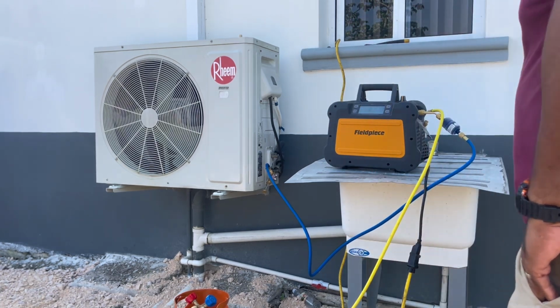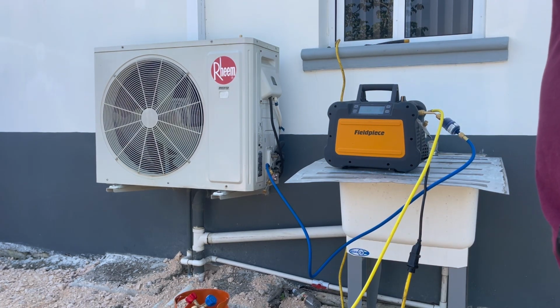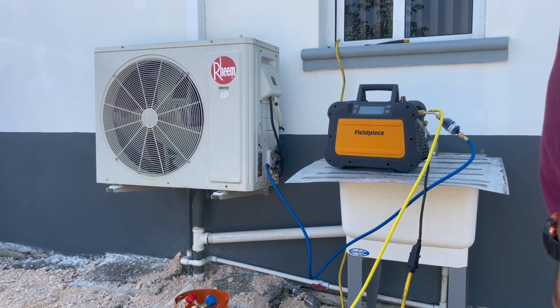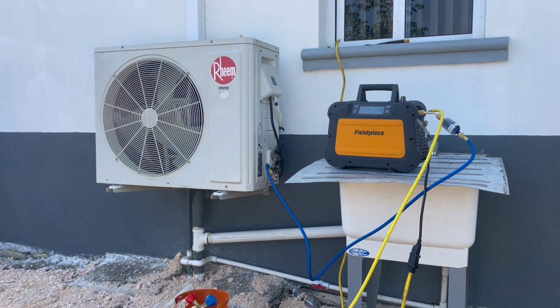My suction line goes to the inlet, and the yellow hose goes to the outlet into the recovery tank. I'm using my scale to measure how much freon comes out of the system. This takes some time to recover the unit because of the size of the unit.